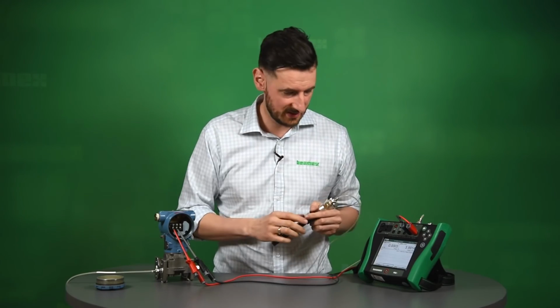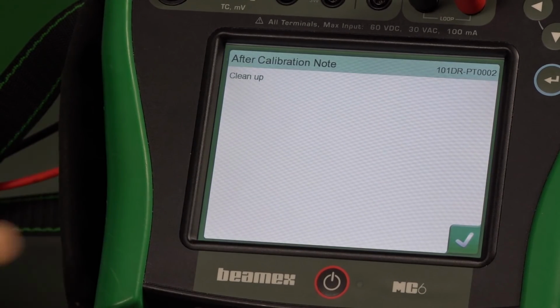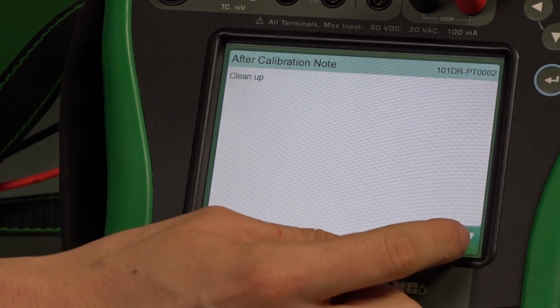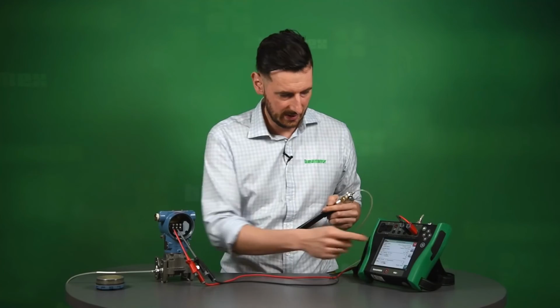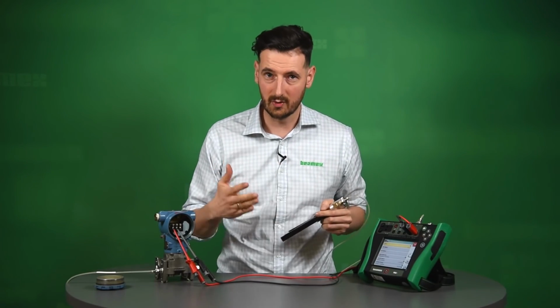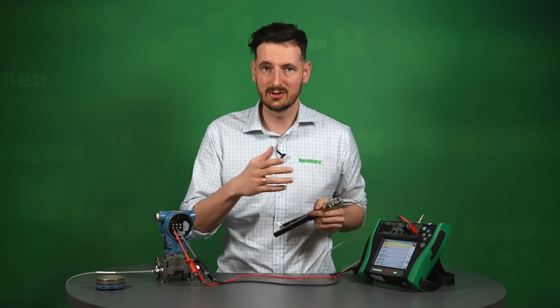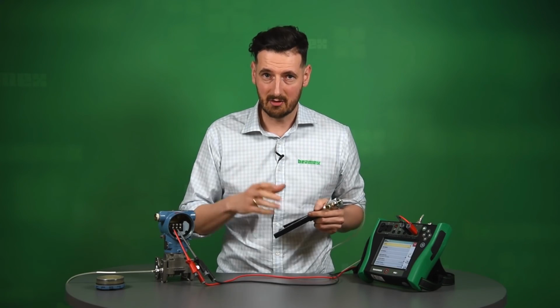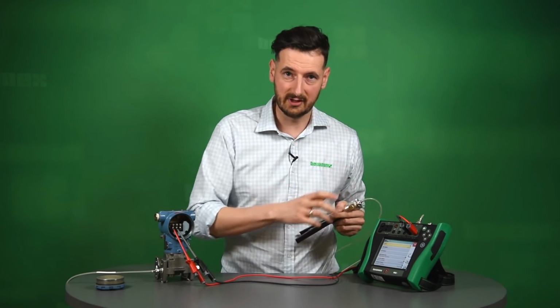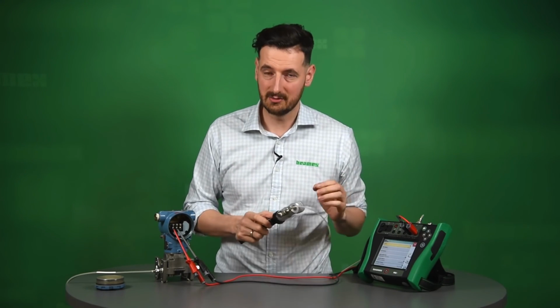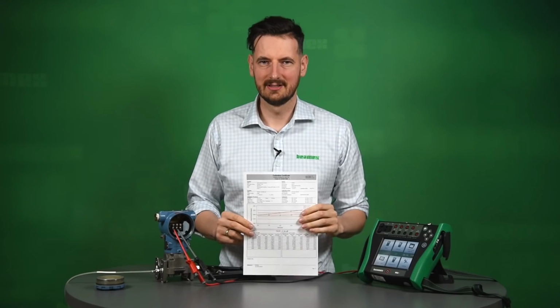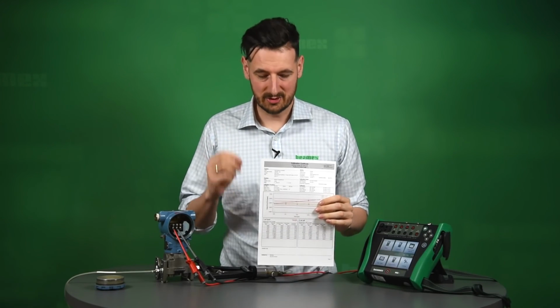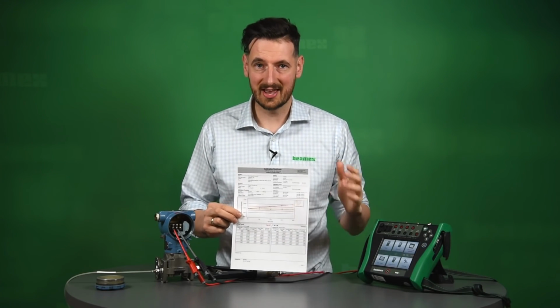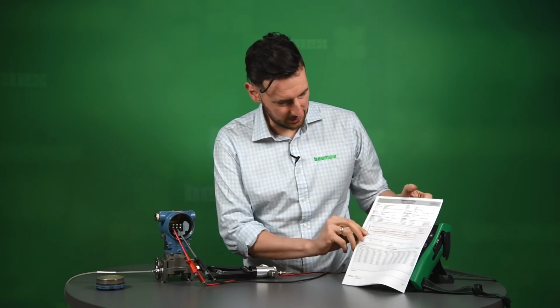So right now we save this calibration, ready to hit back. There is another information about after calibration note, and if we hit X, we're ready to go and start another calibration should we want to do that. Let me show you right now how the certificate of that calibration that we just performed would look like. We just got our results from CMX calibration system. It basically looks like this.